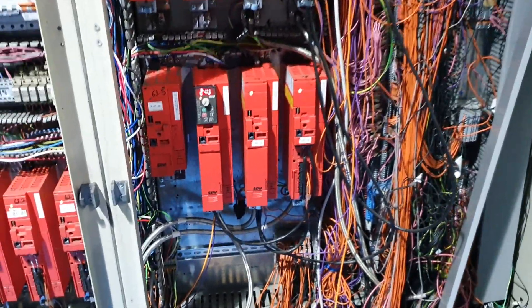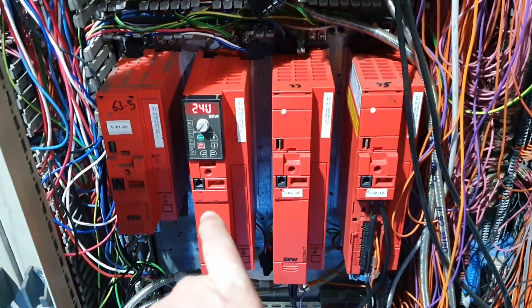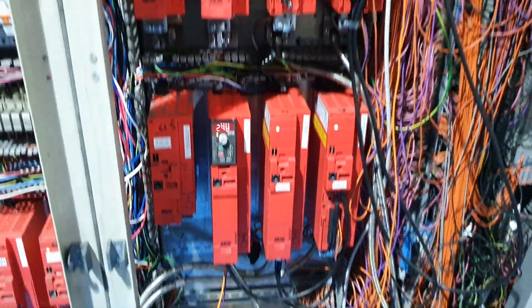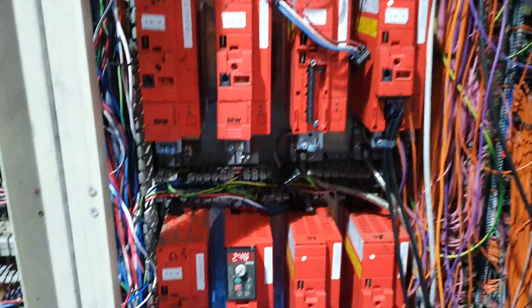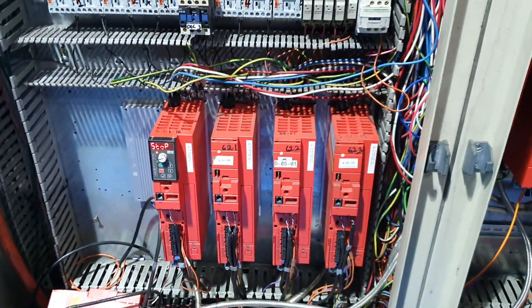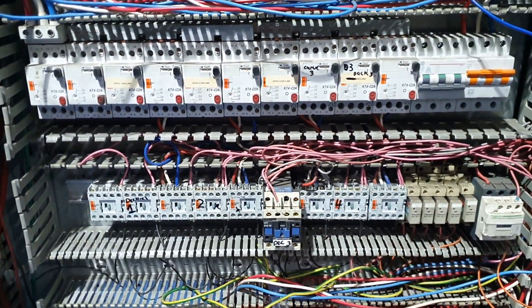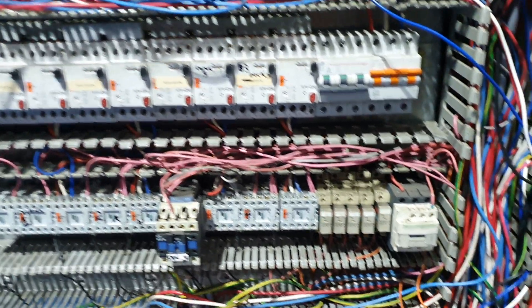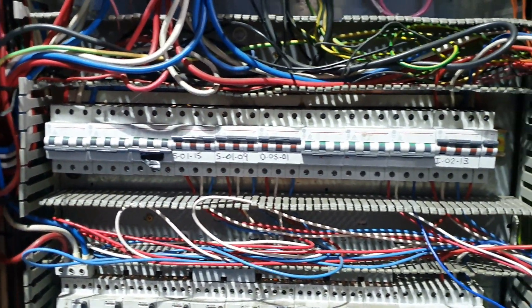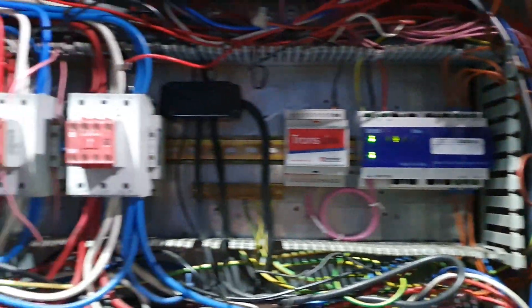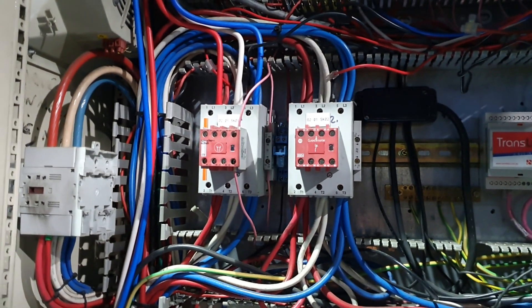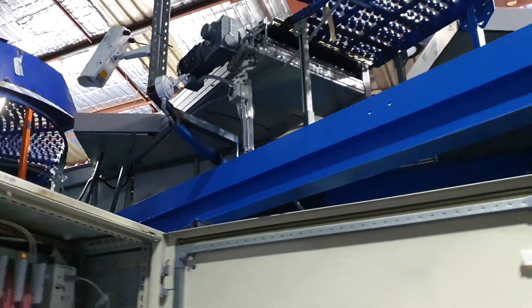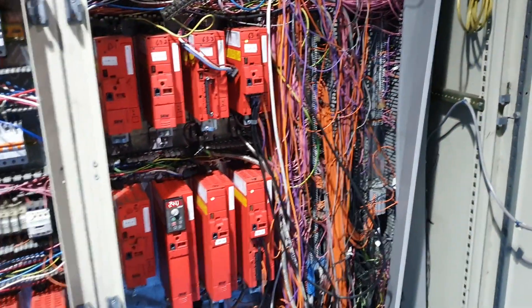It costs a lot of money to fix these things and it's running. So these are SEW VSDs. They control the motors, speed control for the motors on these conveyors. There's a few more down there. And you've got motor breakers and thermal overloads here. Some relays. Some relays there. And your circuit breakers for the motors. There's a C-bus link. Some big contactors to turn the panels on and off. She's alive. She's running. It's good to see.